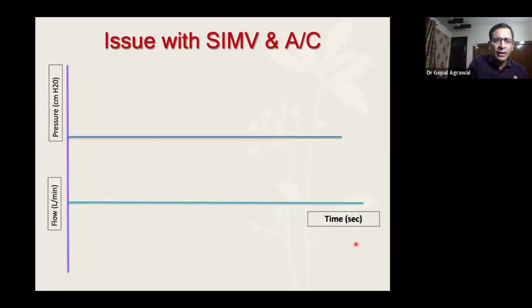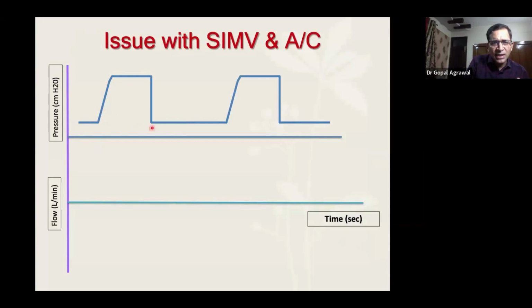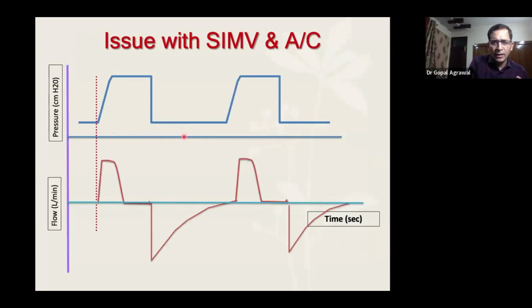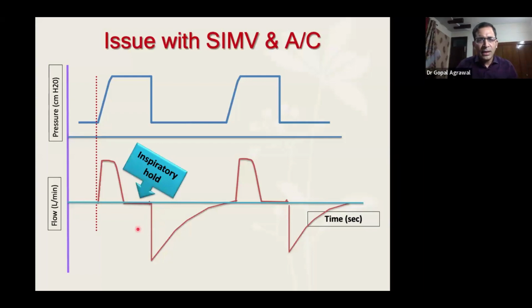Suppose we feel that assist control is better. Let's see. This is a pressure time scalar waveform where this is inspiration, this is expiration. If you see the flow time curve, during inspiration there will be a duration of inspiratory time where effective ventilation will not be there. The breath will be held in peak inflation for some time, which is actually ineffective, and then there will be cycling. So there is a fixed I time and there is something called inspiratory hold, where this duration of breathing doesn't help the baby, and there'll be increased work of breathing because of inspiratory hold.